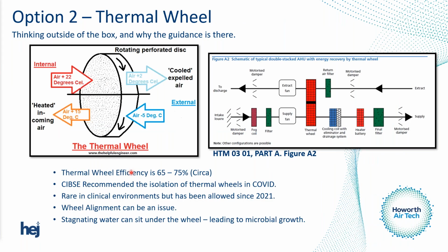The second option that's been given in HTM from 2021 is a thermal wheel. The way a thermal wheel works is that it moves very slowly between the return and supply legs, recovering energy from the return and putting it back into the supply side to reduce the pressure on the heating coil. You can see that all the components are at the bottom of the air handling unit. That's done by design, so if one of these needs changing, it's easier to change. There's not as much lifting and shifting for engineers.